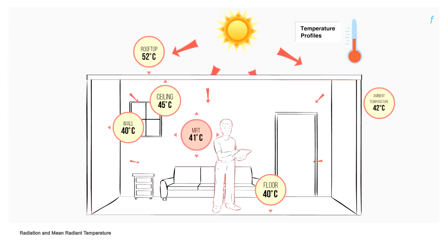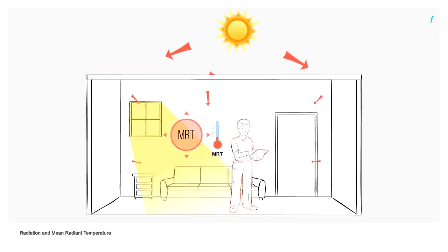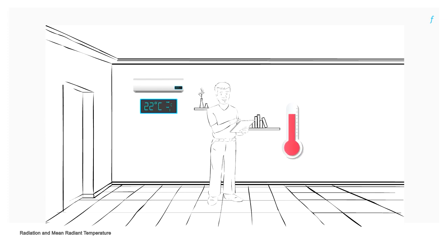Mean radiant temperature quantifies the influence of surface temperatures on human comfort. For example, a hot roof, windows exposed to direct sunlight, etc., will increase the mean radiant temperature. The higher the mean radiant temperature, the cooler the air required to achieve thermal comfort.